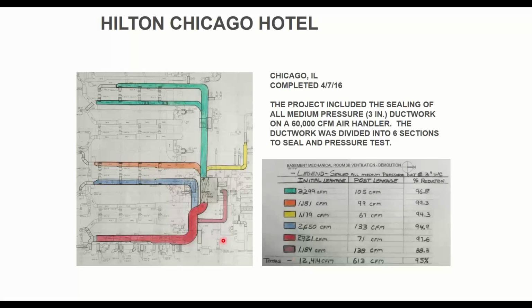It was so big that they couldn't use one Aeroseal machine to seal it all simultaneously. So they had to bust it up into different duct sections. One of the guys made this little color-coded drawing for us to show how they broke up the different duct sections and sealed each one of these branches individually. That way they could generate enough pressure to do it. And then it shows you the initial and post-leakage of each branch.